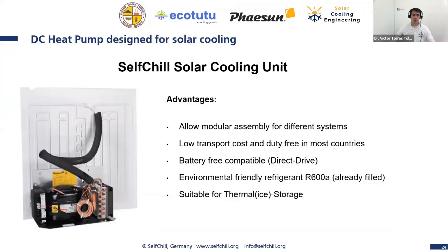Let's have a look here at the cooling unit itself. It has a closed circuit, so we have here evaporator and condenser, but the refrigerant is inside, right? So we are producing cooling energy at this evaporator plate. And then this evaporator plate is in contact with water inside the water chiller, and then is producing ice. And this ice is freezing, then melting, and so on. So freezing during the day, melting at night. And the cold water is used to be pumped inside the cold room.